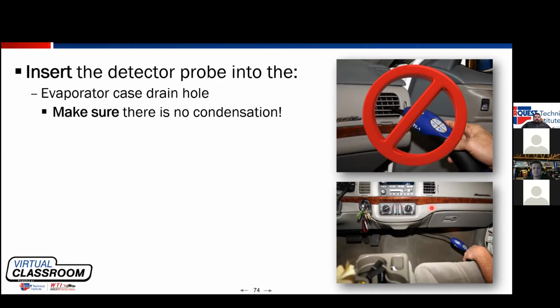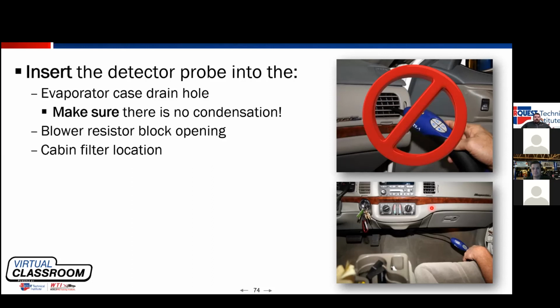One of the big things when you're running that blower fan is we're trying to dry the evaporator core. Moisture will generally false trigger a leak detector. So we want to make sure that there's no condensate in the evaporator core or in the drain that will give us a false positive. Again, patience. Let that refrigerant accumulate. Let it get to the tip of the leak detector.